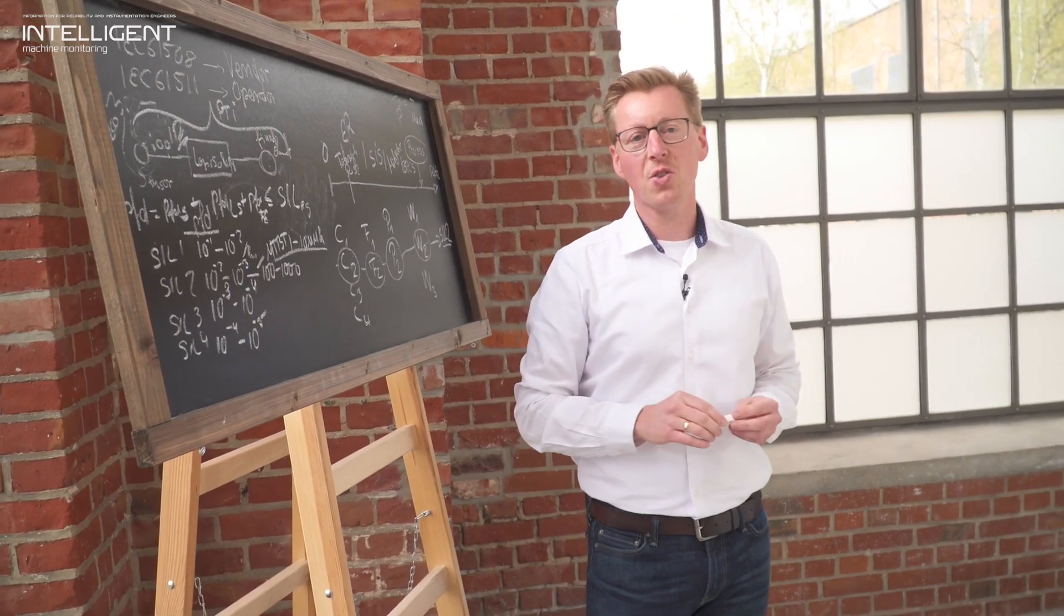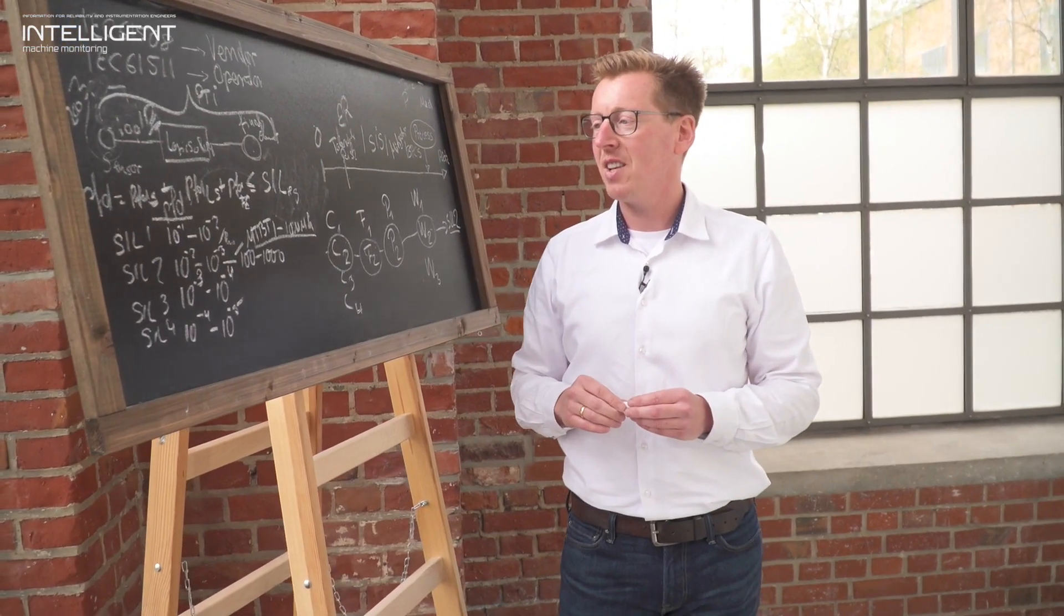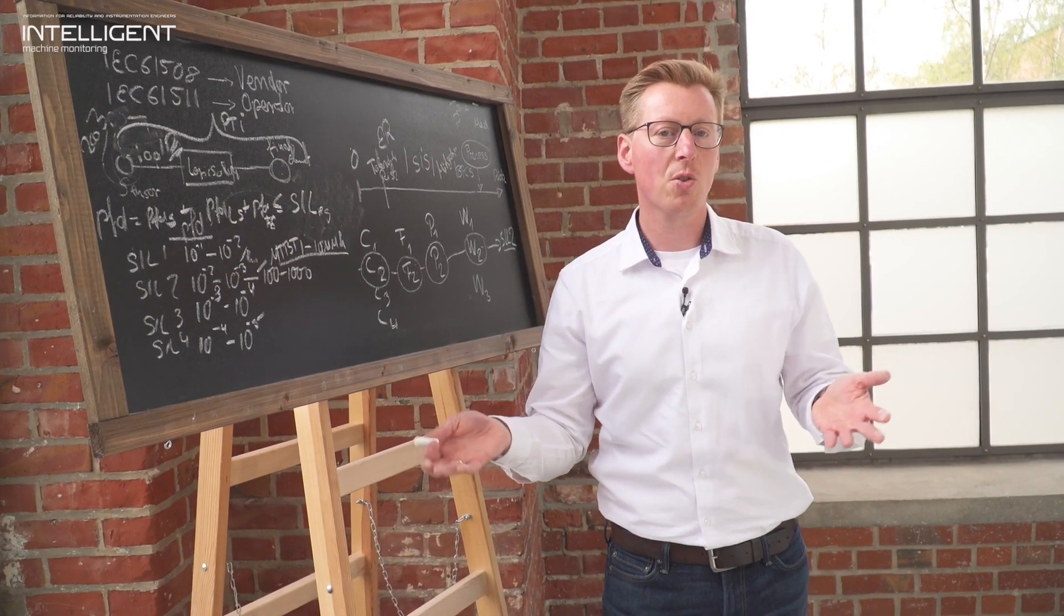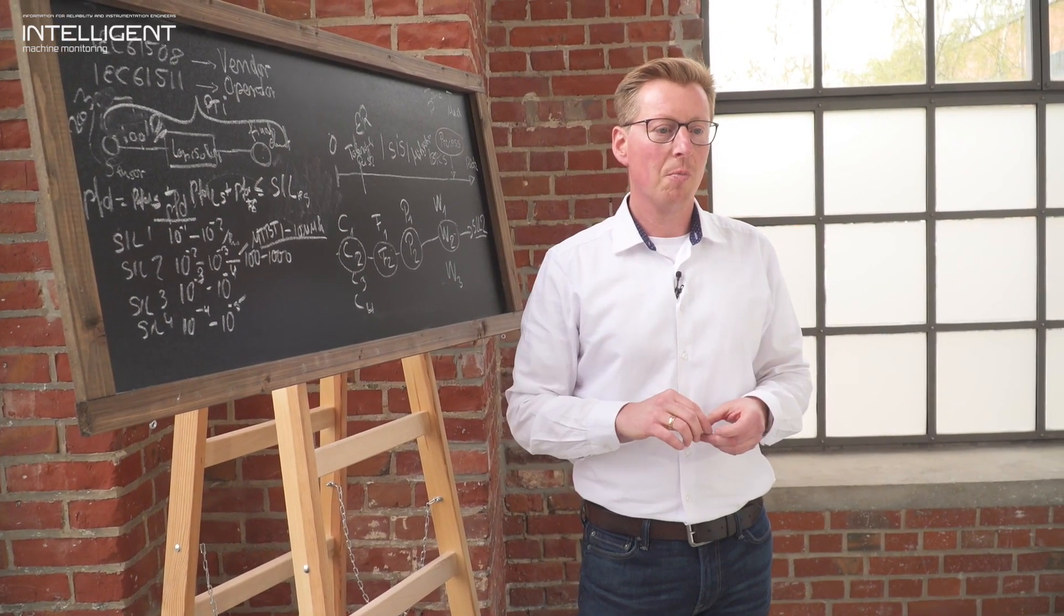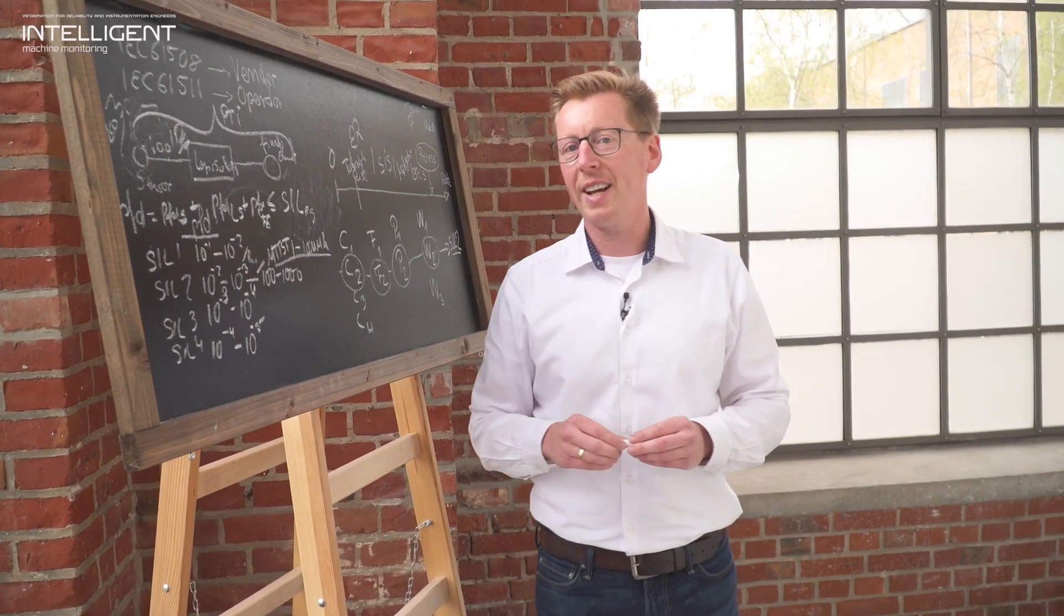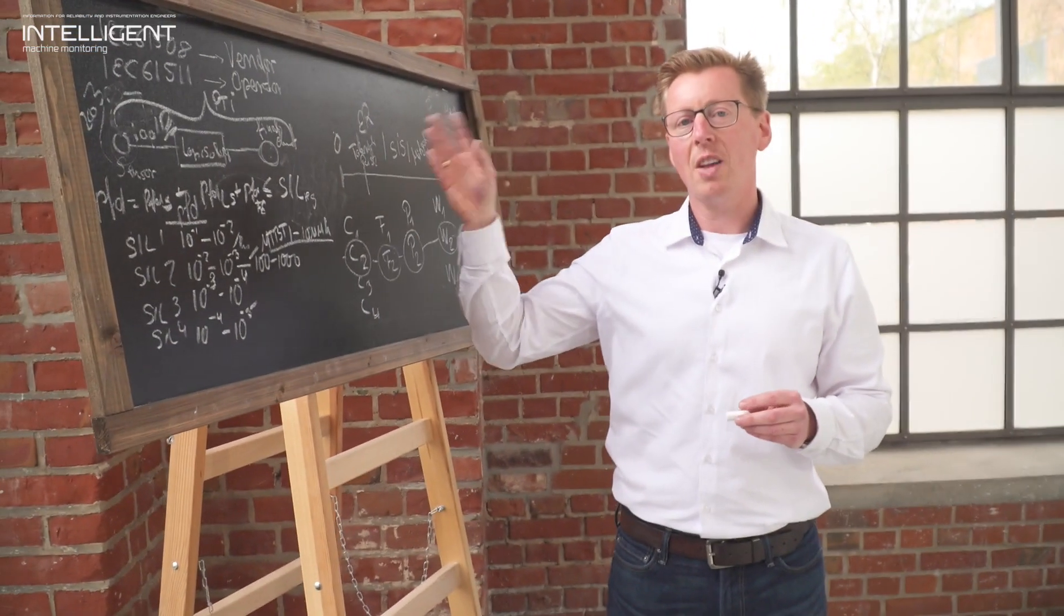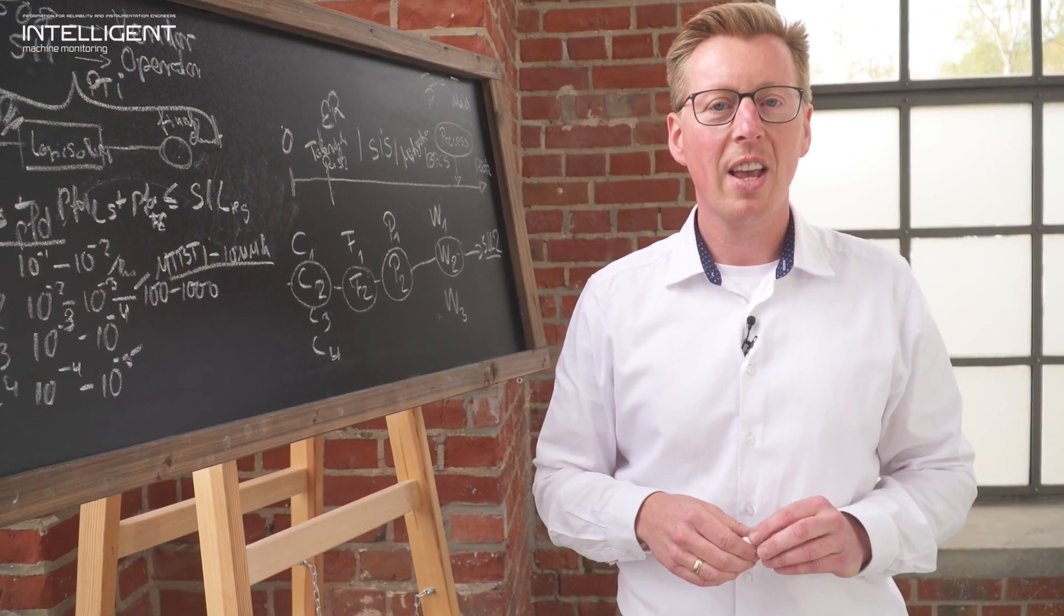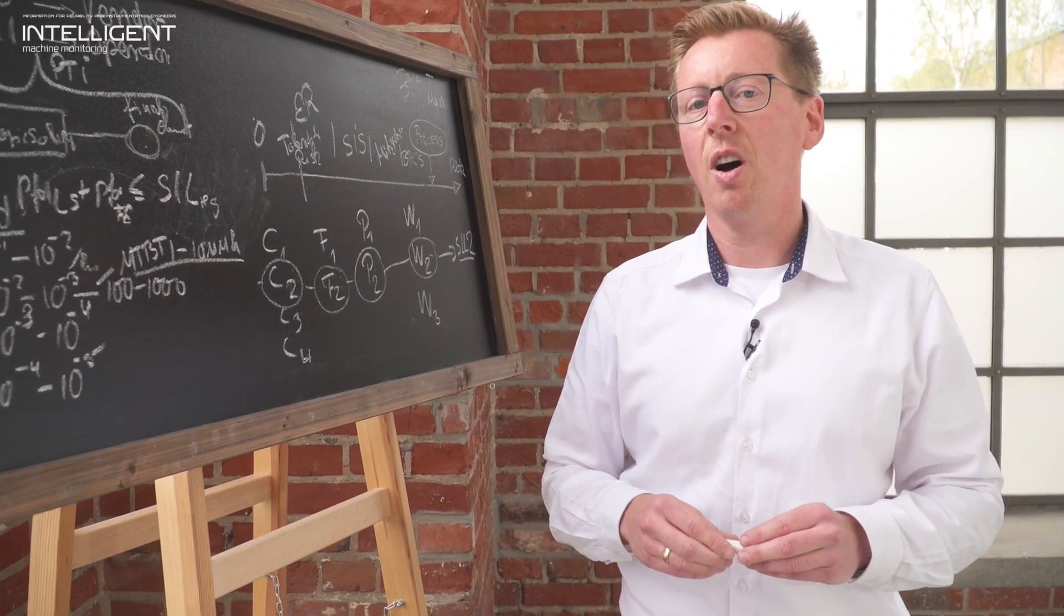In turn, I would also say it's even more important, rather than SIL certification, it's more important having a system in place that is appropriate for the application. Imagine you had a large critical centrifugal compressor, a recip compressor, and you would equip that with a SIL 3 gas temperature sensor. This would lead to no good, because the sensor or the system itself is not appropriate to detect any mechanical issues early enough to prevent the catastrophic damage. You'd rather want to have a system that is fit for purpose. So I would recommend to adhere to the OEM standards and to do what's best for the application to capture these problems reliably on time.